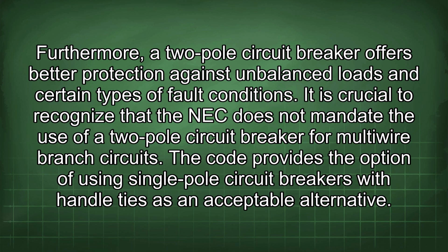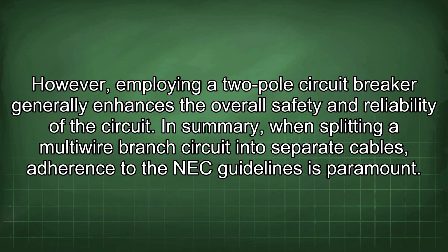It is crucial to recognize that the NEC does not mandate the use of a two-pole circuit breaker for multi-wire branch circuits. The code provides the option of using single-pole circuit breakers with handle ties as an acceptable alternative. However, employing a two-pole circuit breaker generally enhances the overall safety and reliability of the circuit.